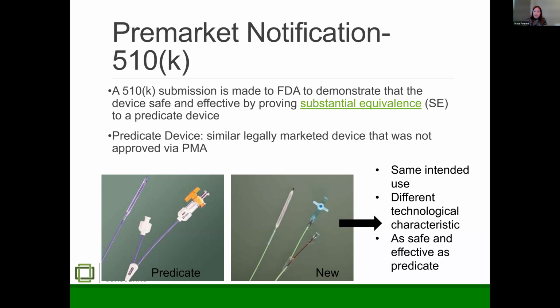There's a piece of it that's not the most logical in my mind, but it's still what the process is. And that's the concept of substantial equivalence. So a 510(k) submission is made to FDA to demonstrate that the device is safe and effective by proving it is substantially equivalent to a predicate device. So substantially equivalent means that it is similar to a legally marketed device that was not considered a high risk device. And so that's kind of a strange concept.